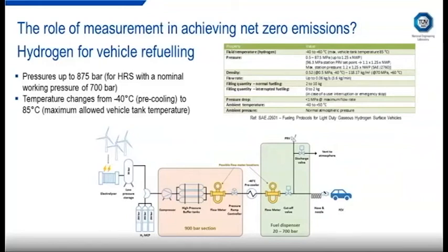So because we need to achieve a good energy density, the hydrogen has to be compressed. In the vehicle, it will be compressed to around 700 bar for a light-duty passenger car. So within the refueling station itself, you can have pressures of up to 900 bar. The refueling process is also very quick, which means you generate a lot of heat when you compress the gas into a tank. So to prevent the temperature rise from being excessive, the hydrogen is first pre-cooled down to -40 degrees C. So these ranges of pressures and temperatures are not easy for most flow meter technologies.